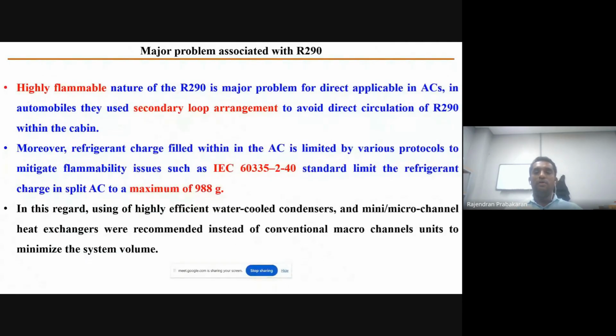So many protocols have been introduced to reduce the flammability issues by minimizing the refrigerant charge. According to the new IEC standards, they set a maximum limit of 0.988 kilograms of R290. Moreover, using water-cooled condensers and high-efficiency mini-channel heat exchangers, including plate heat exchangers, helps reduce the overall system volume and directly reduces the refrigerant amount. So these are all the strategies being followed to implement R290 in real building cooling air conditioners.